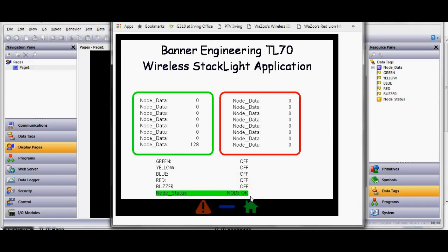Now the node is powered off. Eventually, the gateway is going to, look at there. It says, hey, I got a node error because I turned that guy off. So that's a lot better than this. This doesn't mean anything to the operator, but this does. This is perfect. I could have also put loss of power or something, but I just left the text as node error.